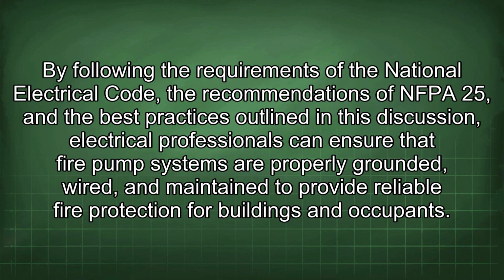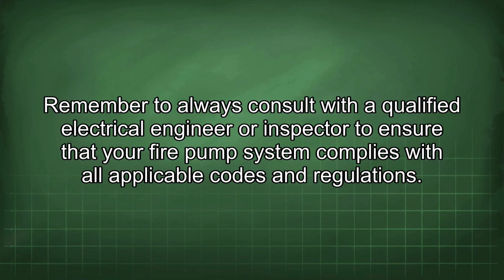By following the requirements of the National Electrical Code, the recommendations of NFPA 25, and the best practices outlined in this discussion, electrical professionals can ensure that fire pump systems are properly grounded, wired, and maintained to provide reliable fire protection for buildings and occupants. Remember to always consult with a qualified electrical engineer or inspector to ensure that your fire pump system complies with all applicable codes and regulations.